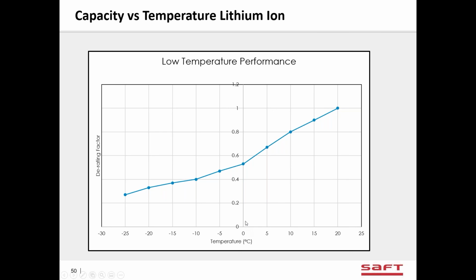you have to know that so that when you size the battery, because if you discharge the battery at 0 degrees C, you're only going to get about half of the capacity. So you have to size knowing the temperature of the environment.